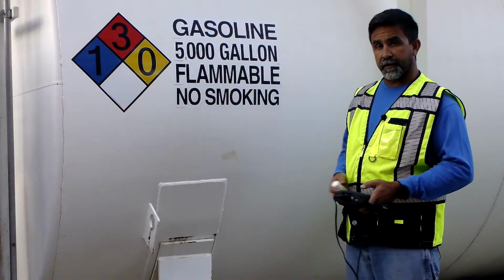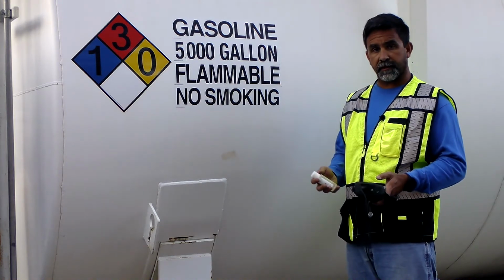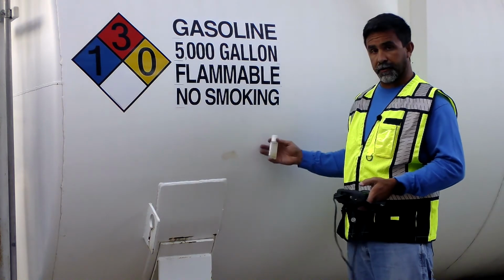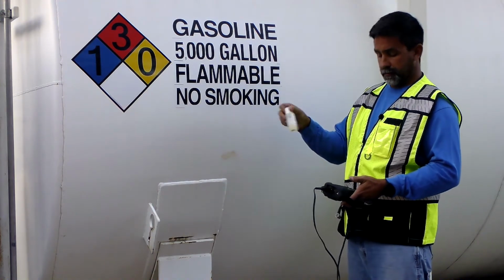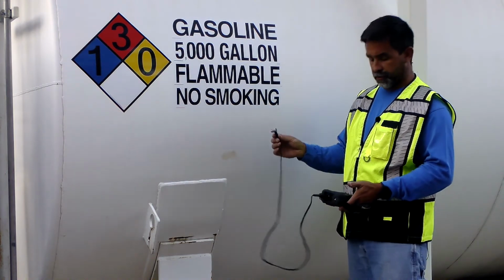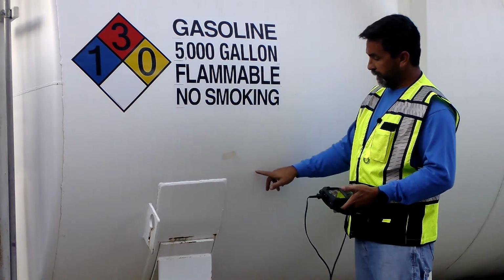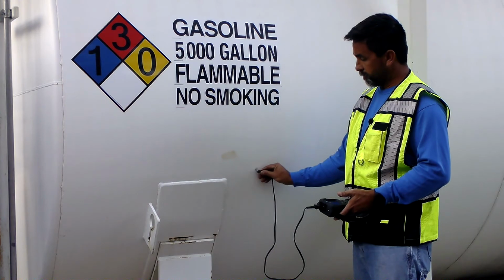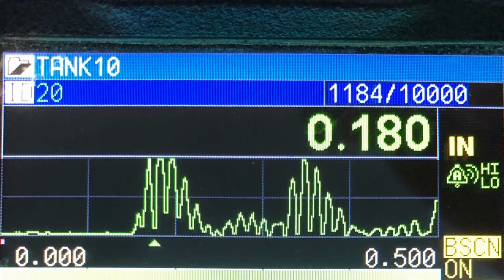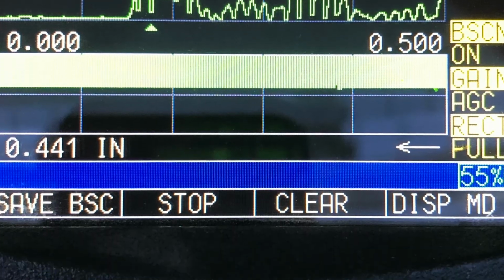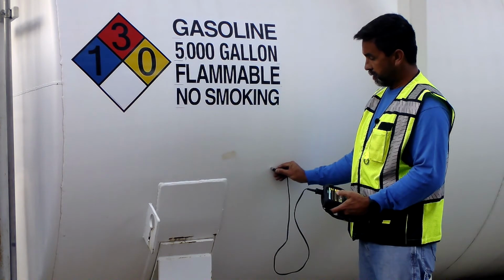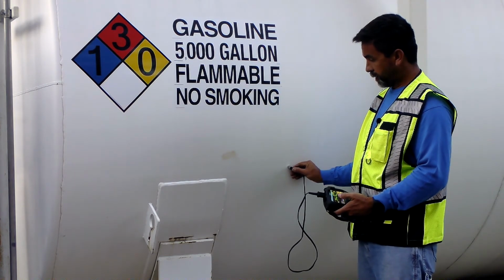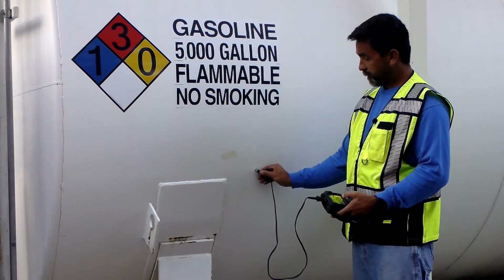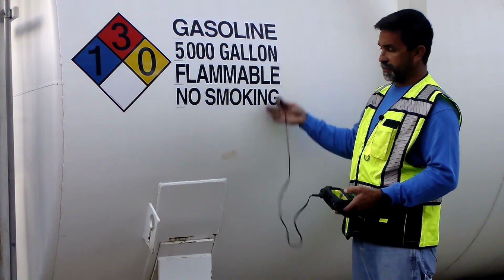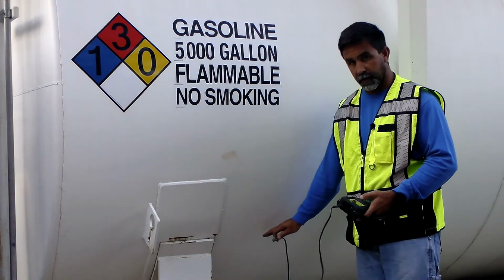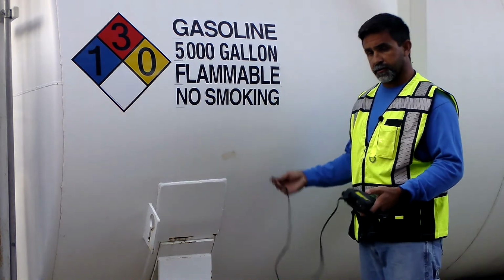Following up, now that we've identified that there is water in this double wall tank, we need to perform ultrasonic thickness testing, and this is a quick demonstration of that on this outer part of the tank. So we have our couplant, we have our ultrasonic thickness device with the transducer. We would apply a liberal amount of couplant, hold the transducer to the surface, read the steel and identify the thickness with A scan or B scan to ensure that there is not corrosion from the inside out due to the water. This is typically done on the lower third of the tank, and after you get these results, they all need to be inputted into the report.